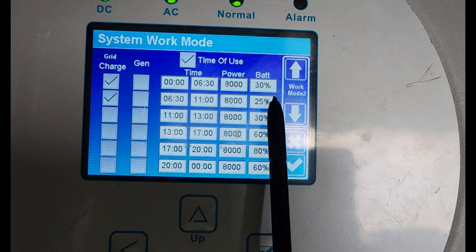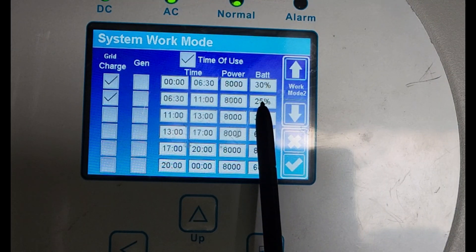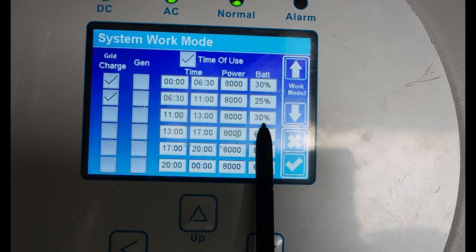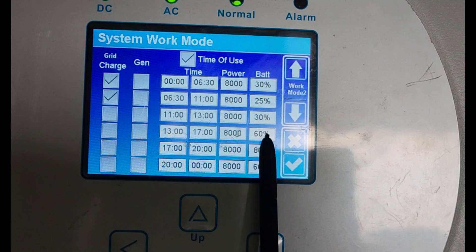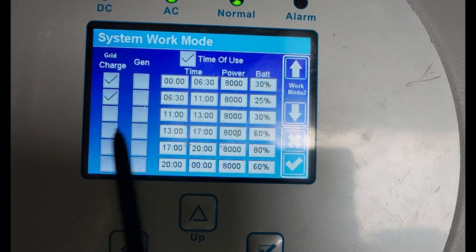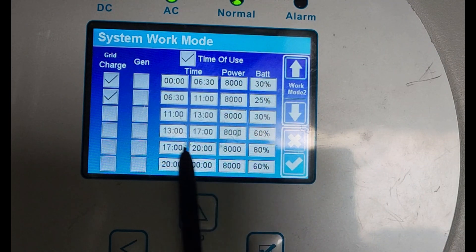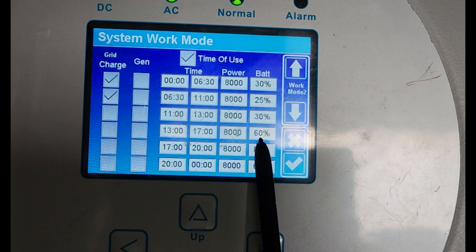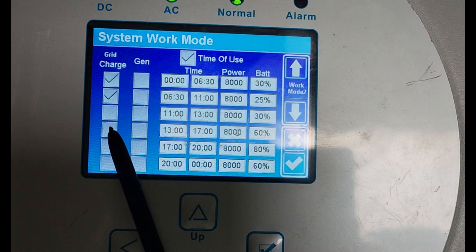Otherwise I expect it to go down to 25 — if it tries to go below 25, it will not go below 25. The only thing that'll happen is the grid will take over. So just for interest sake: if you go to 30% and the sun drives it to about 40%, and this period then kicks in — it isn't 60 because it's not ticked. It will not push up to 60. If it was ticked, it would push it up via grid to 60. I don't want to do that because I don't want to charge with the grid and then discharge the battery — charge with the grid, discharge the battery — you're adding cycles to the battery, and that doesn't make sense. So if it's at 40 and there's a power out, it's at least 40 as a backup for an hour or two. So I don't tick the ones later in the day.